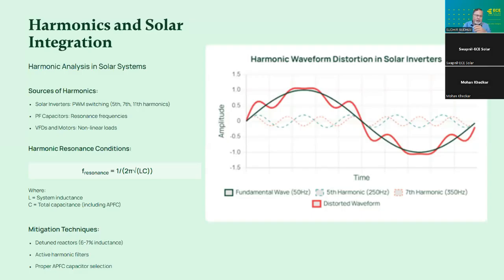So the calculation formula is very simple. Frequency of resonance will be 1 by 2π under root LC. To mitigate this problem, what we suggest is to have a detuned reactor of 6 to 7%. And if the problem is complex, you can have an active harmonic filter also.